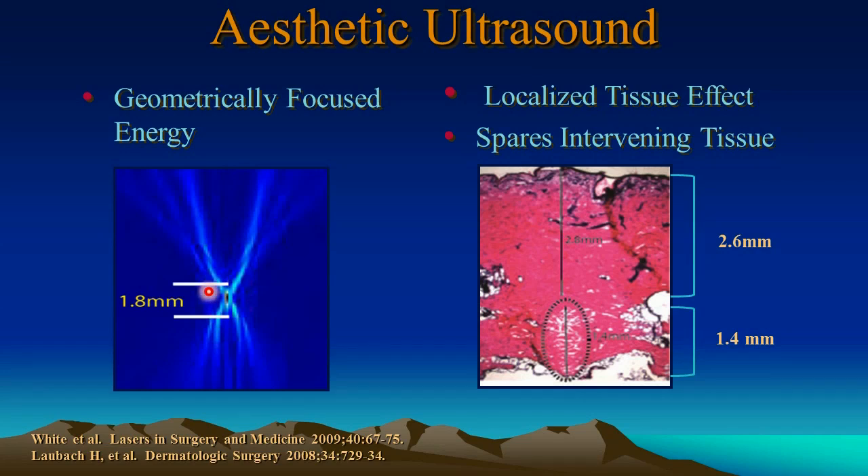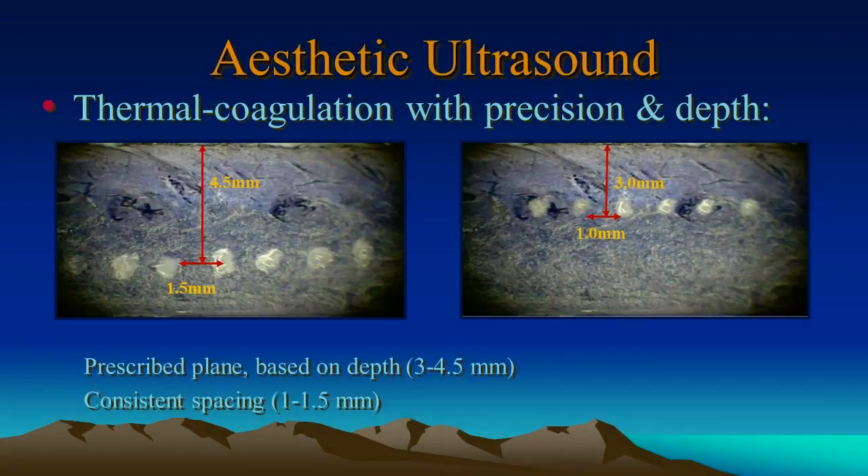The geometrically focused energy can be very precisely administered. As you can see in this diagram, it's 1.8 millimeters in height, and 95% of the focused energy will be focused within this region. On histology, for example, using this device on pig skin, you can see a very precise, deep injury 2.6 millimeters below the surface of the skin, and 1.4 millimeters in length. In this example, it's 4.5 millimeters deep with spacing of about 1.5 millimeters between each discrete thermocoagulation point. On this side, it's 3 millimeters deep with 1 millimeter separation.